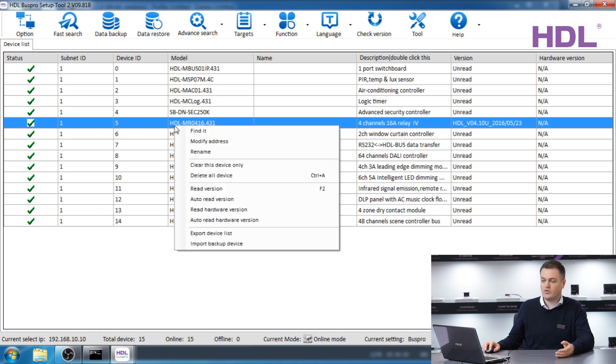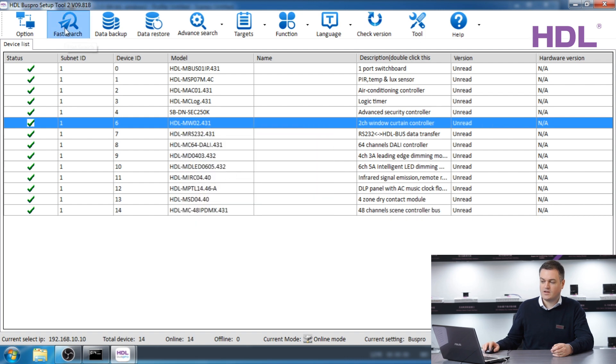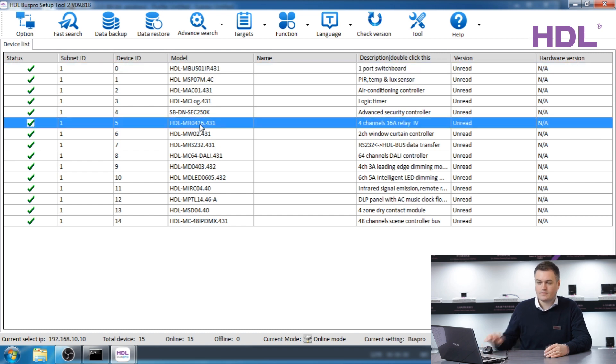Close the window and right click on the device, read version and you can see this slightly different version appears. We always recommend to right click, clear the device, press fast search and add the device back in after the upgrade, because the software will then recognize any changes for when you are programming. If you have any further questions please contact HDL technical support. Thank you.